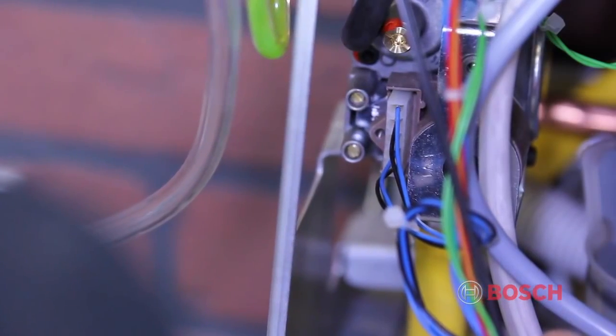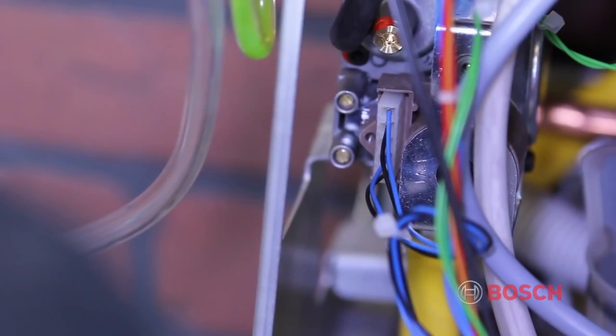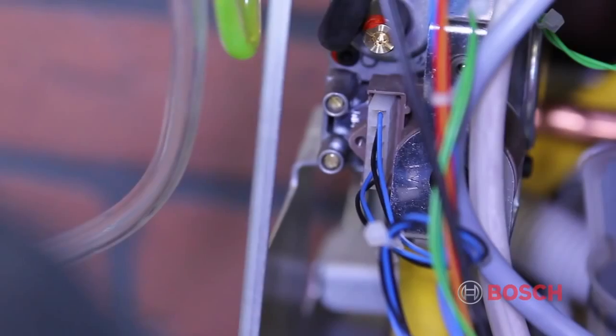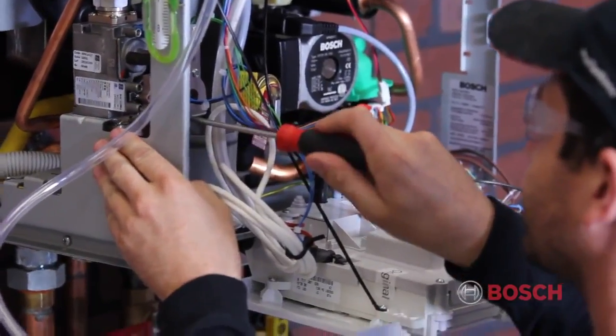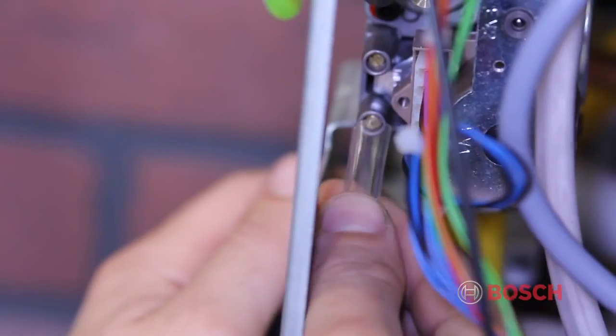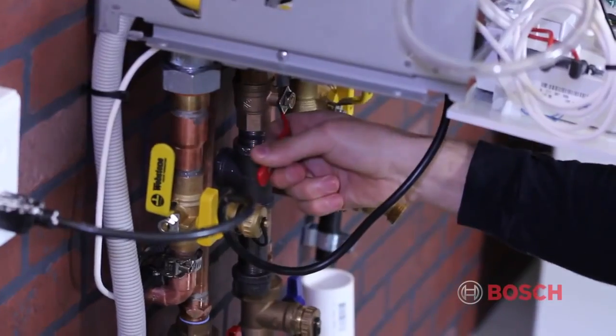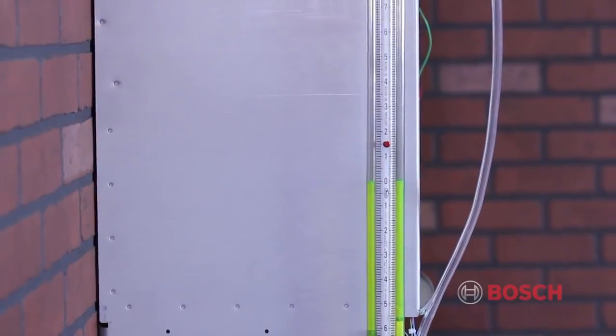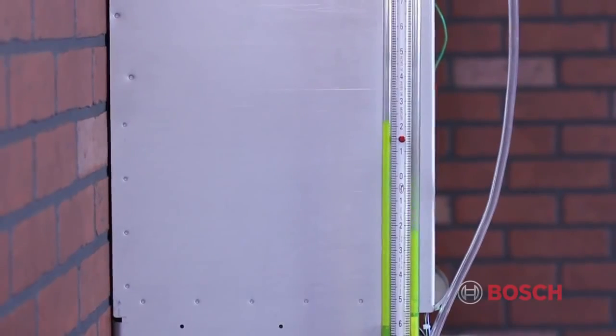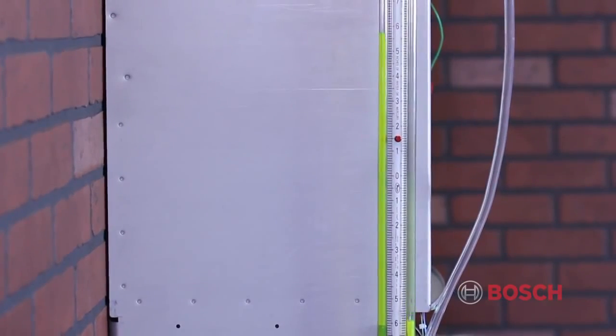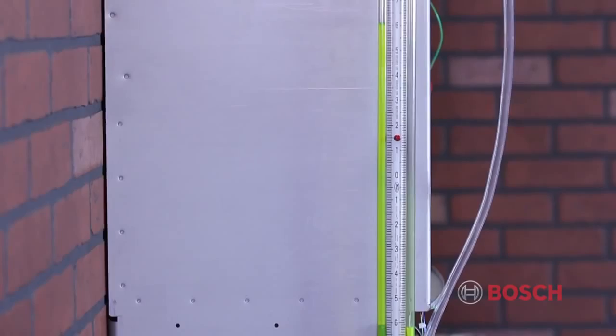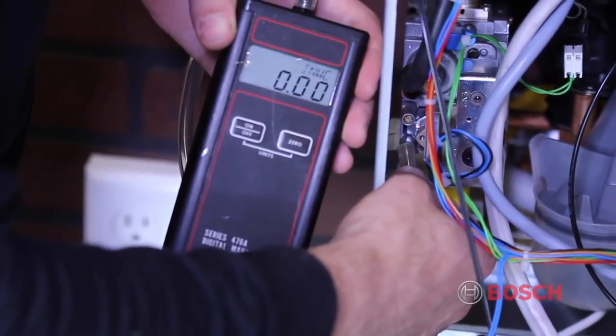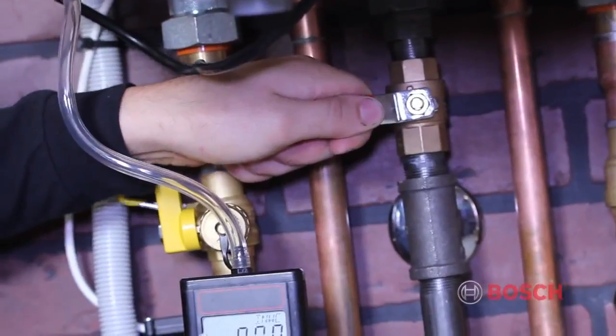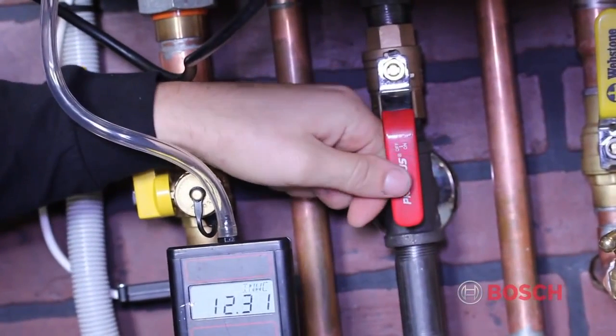On the bottom left of the valve, you will see 2 flathead screws recessed into the gas valve. Loosen the lower screw 2 to 4 turns, but do not remove it. Slide your manometer tube over the test port and turn on the gas. If you're using a slack tube manometer, zero your manometer and add the difference above and below 0. This will tell you your incoming gas pressure. If you're using a digital manometer, attach your extension tube to the gas valve and read your digital display.